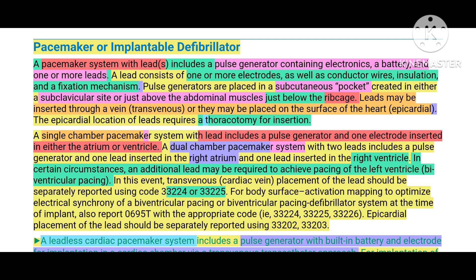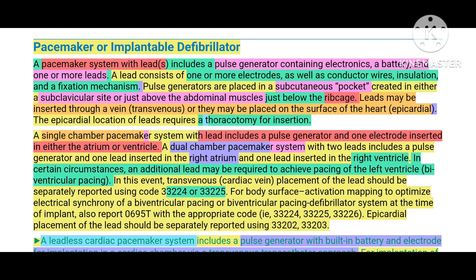A pacemaker system with lead or leads includes a pulse generator containing electronics, a battery, and one or more leads. A lead consists of one or more electrodes, conductor wires, insulation, and a fixation mechanism. The pulse generator is a battery placed below the skin within a subcutaneous pocket, created either at a subclavicular site or just above the abdominal muscles below the ribcage — usually below the collarbone or just below the ribcage in the abdominal muscle region.